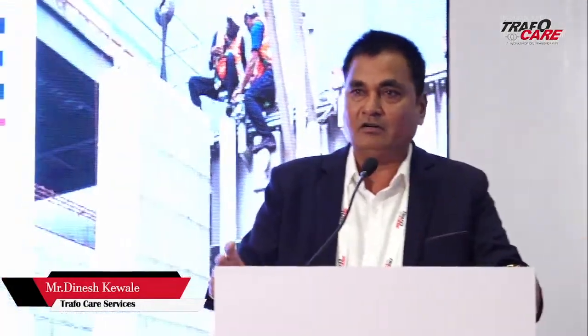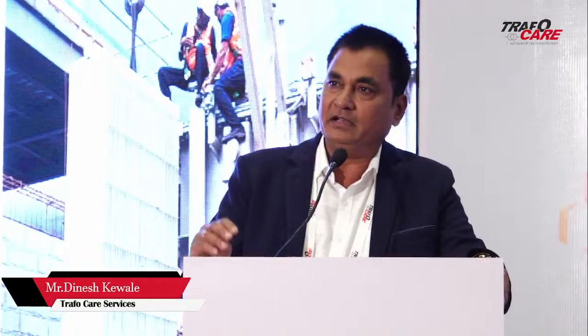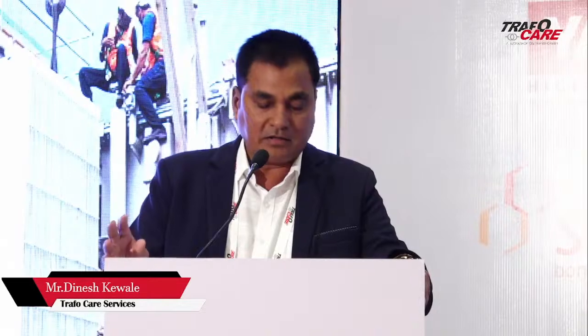So Rajamani sir said at the start that the transformer should be kept on a fixed tap, not in operation. So this fear is there in utilities also: nobody is operating the transformer tap changer or regularly maintaining it. They have a tap changer but the fear is there not to operate it, because during operation some failures have come, so people just maintain it and do not operate it regularly.